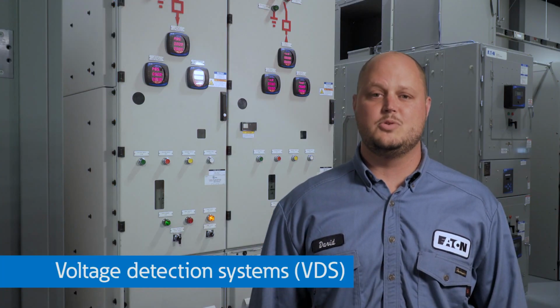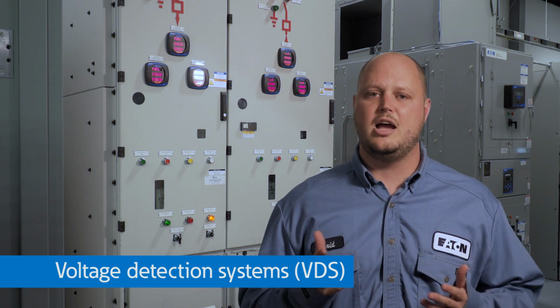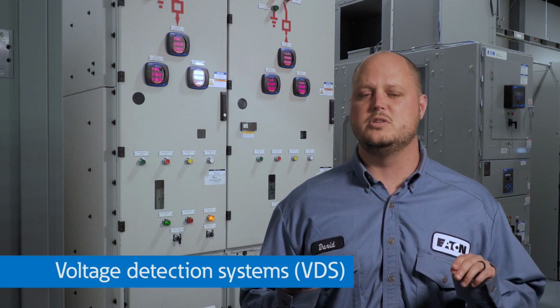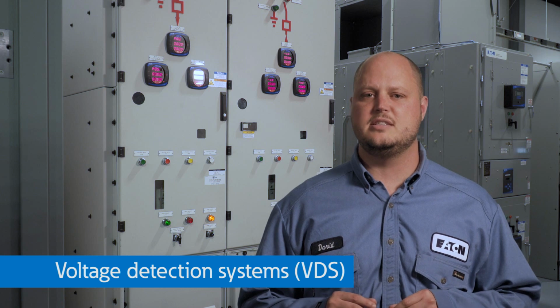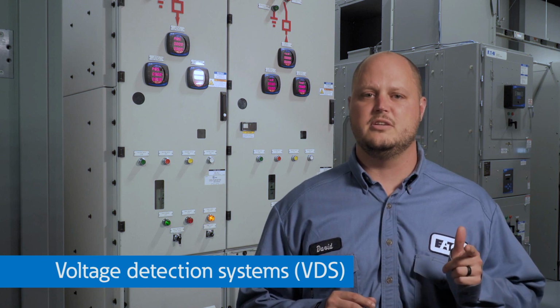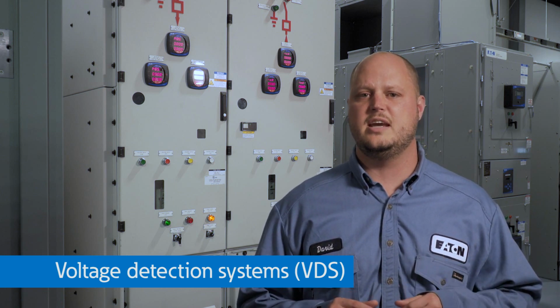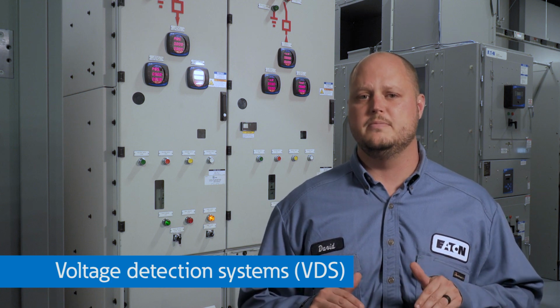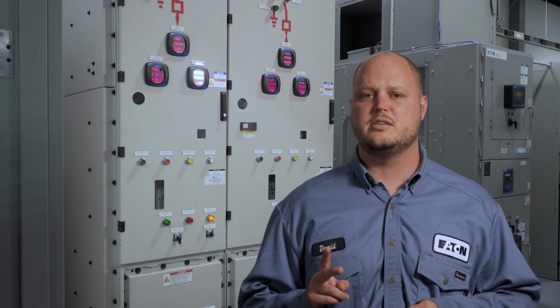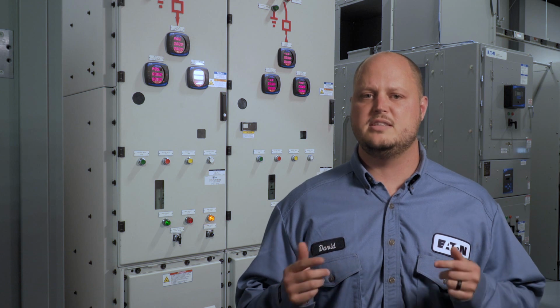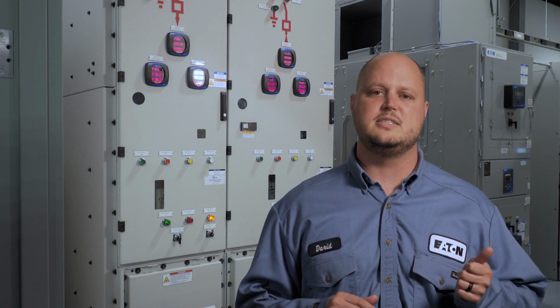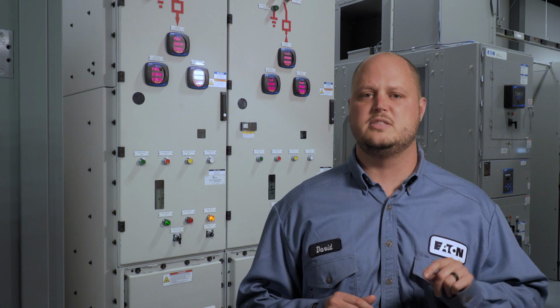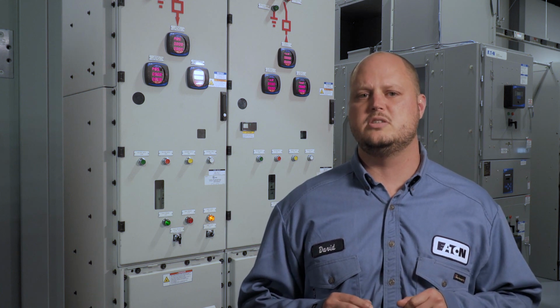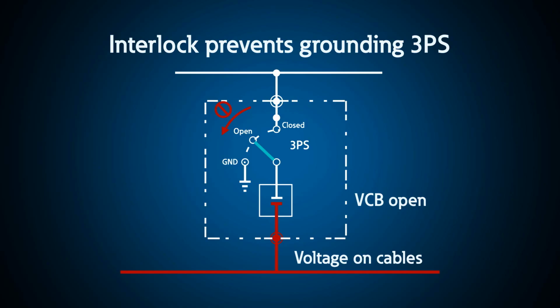Voltage detection systems, or VDS, provide a means to reliably check the absence of voltage in switchgear. A VDS system is included as a standard feature of xgis to detect absence of voltage in the cable compartment. There are also 2 interlocks that incorporate feedback from the VDS systems, both of which are related to safety. The first interlock prevents an operator from grounding the 3-position switch when voltage is present in the cable compartment. This prevents the operator from inadvertently creating a ground fault.